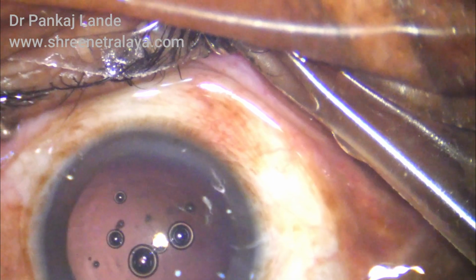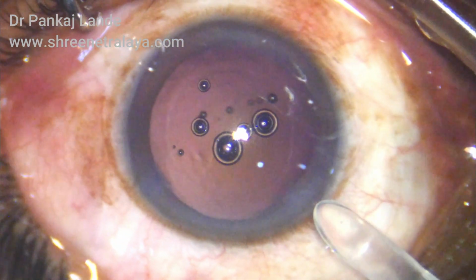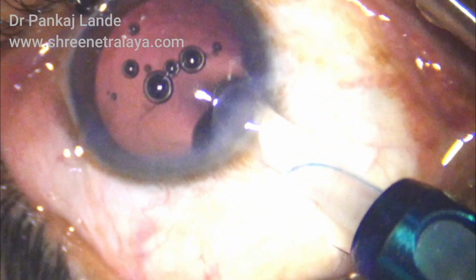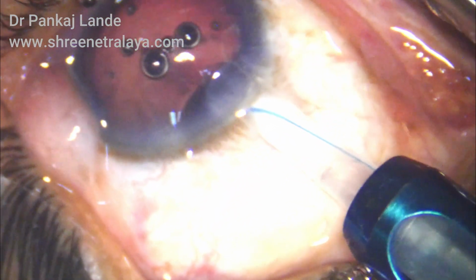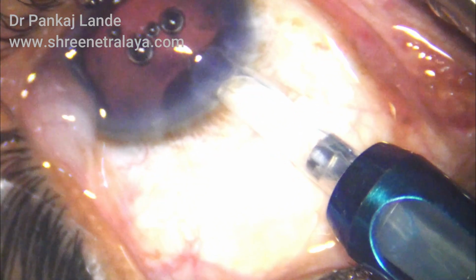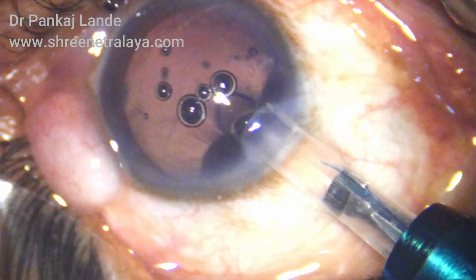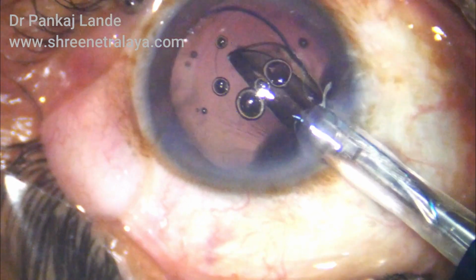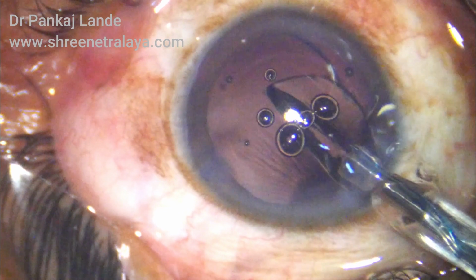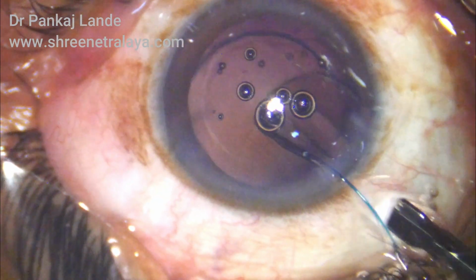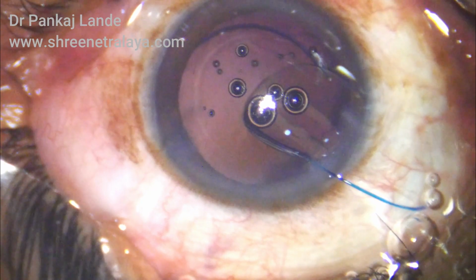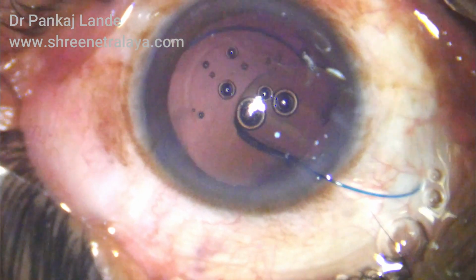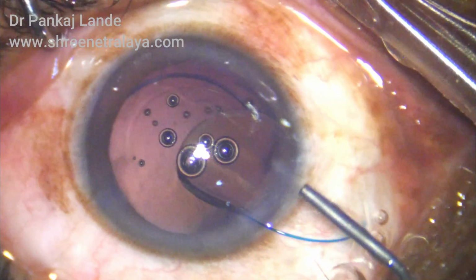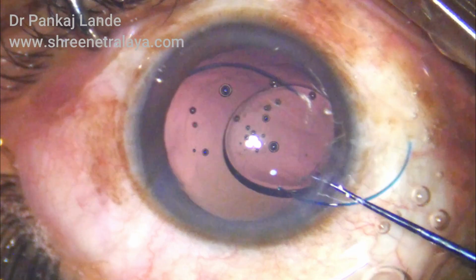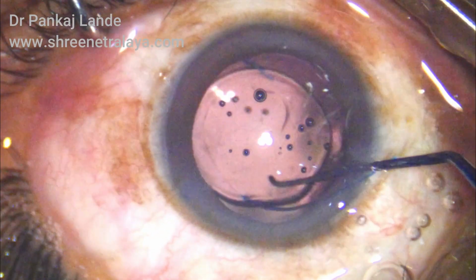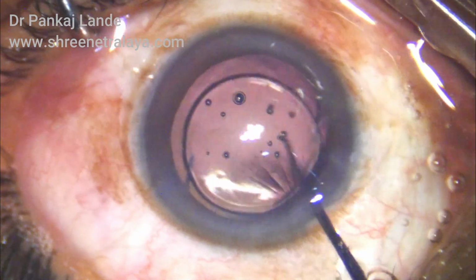Once you have loaded the cartridge, check it under the microscope to make sure optic is well in the groove and both the haptics are in position without having a C loop. Now you can load this cartridge into the plunger and carefully engage the plunger with the optic of IOL without getting your haptic into it. It is very important that your trailing haptic should be lying behind and it should not be engaged in your plunger.